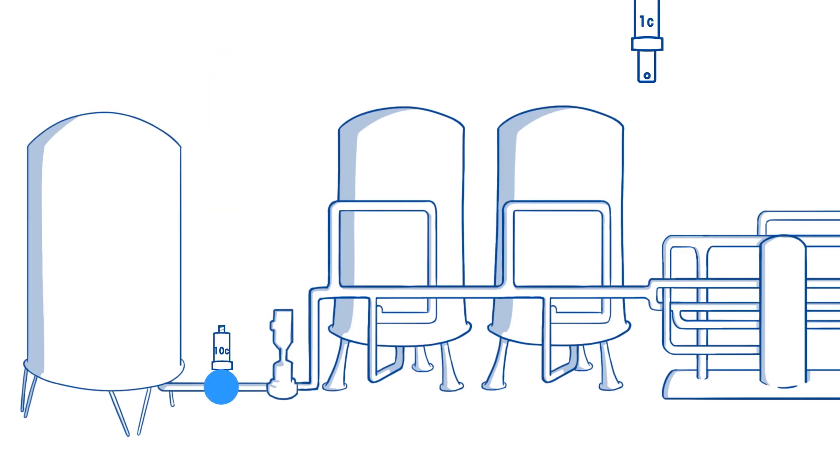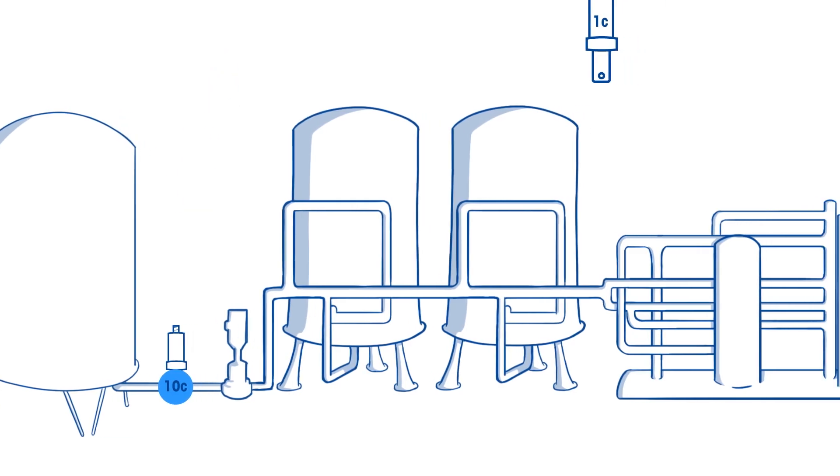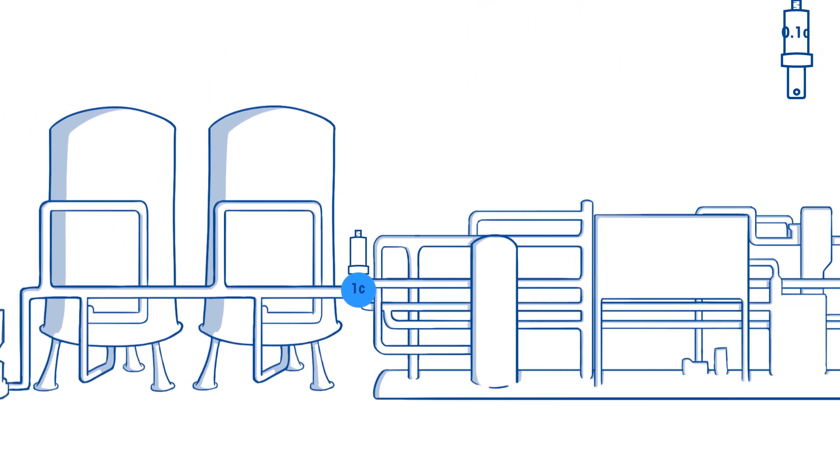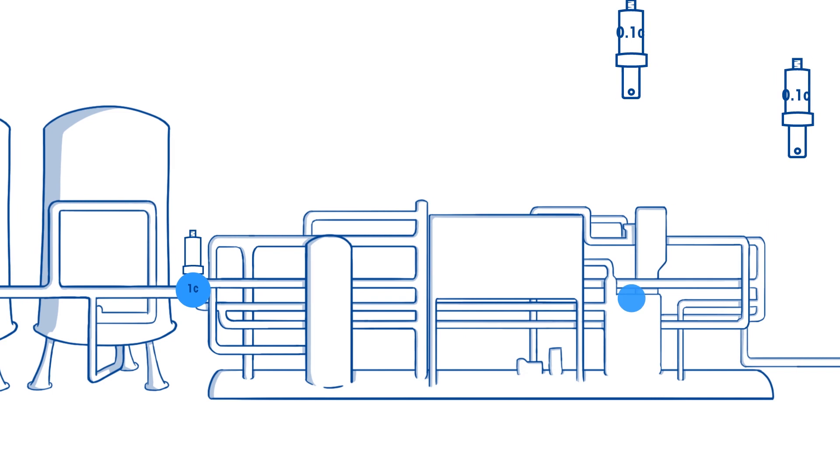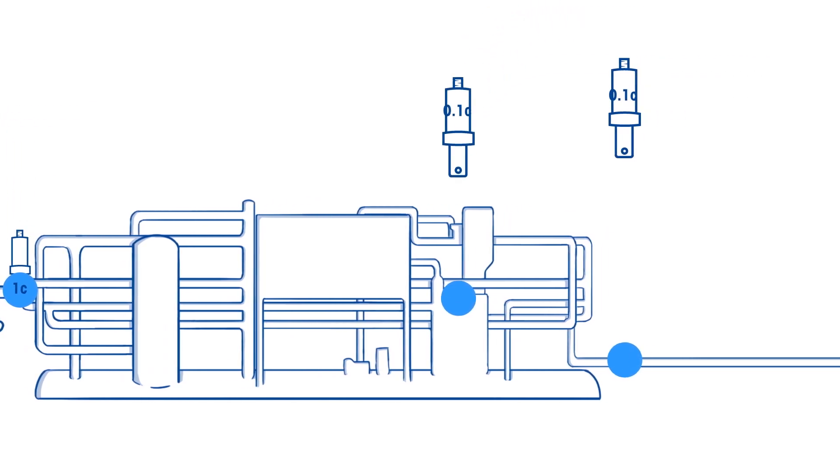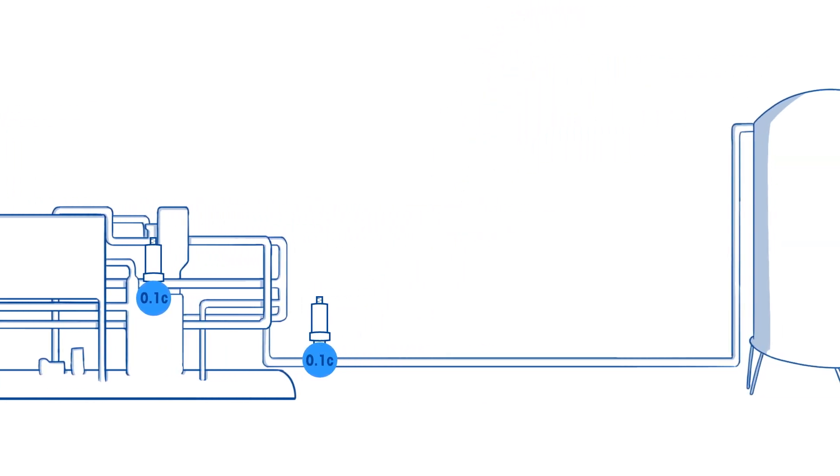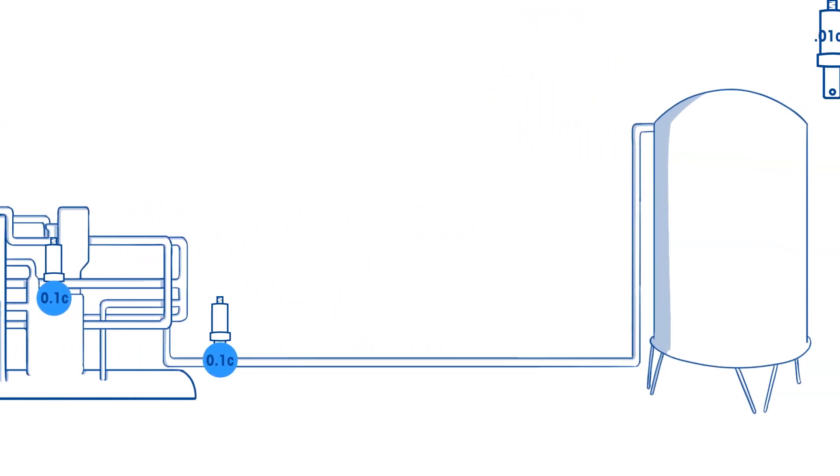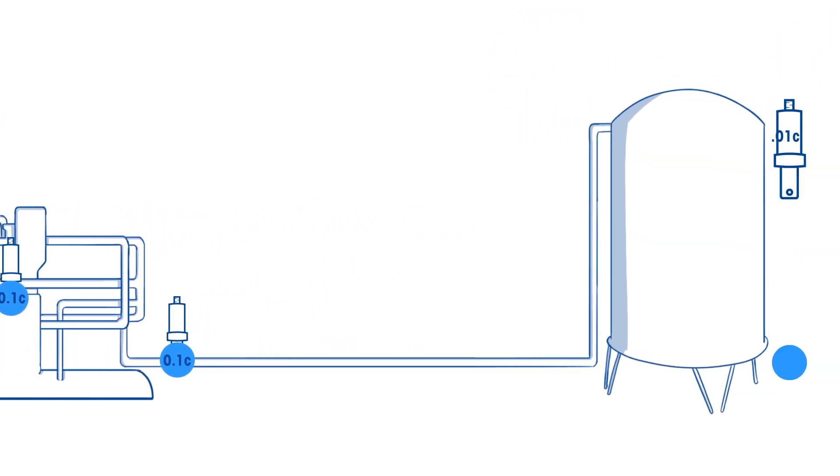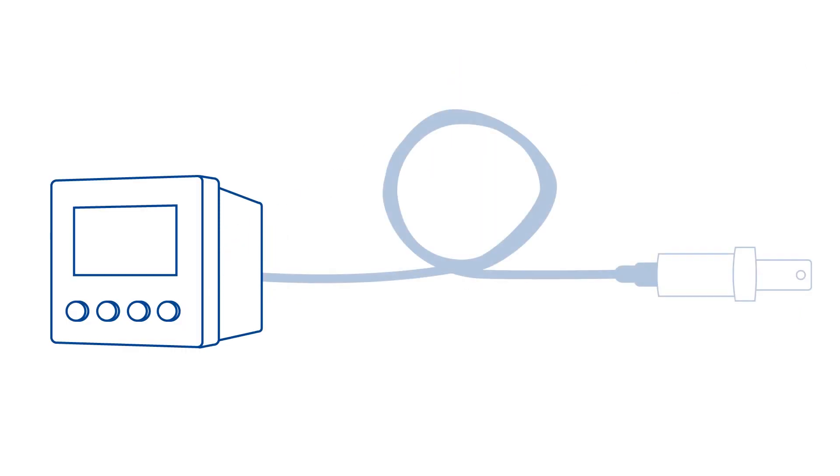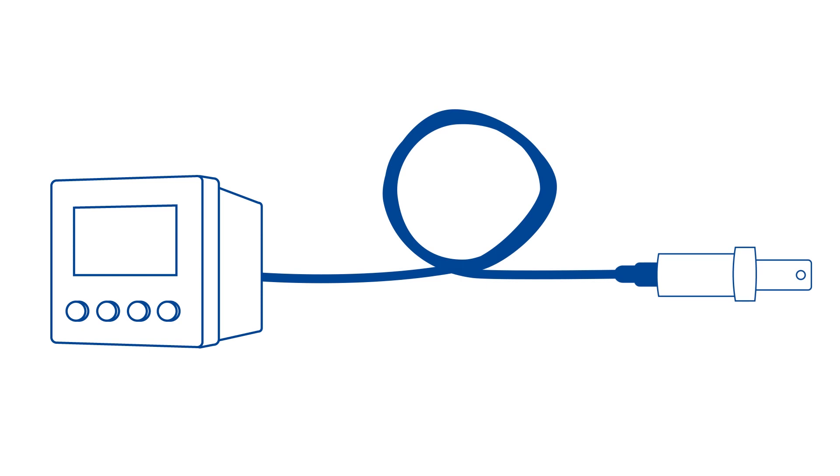With such a wide measurement range to cover, conventional analog conductivity instrumentation requires a series of different conductivity cell constants optimized for each stage of treatment. Analog instrumentation also has the measuring circuit located in the transmitter at the far end of the cable, which puts restrictions on cable length in order to prevent signal deterioration.